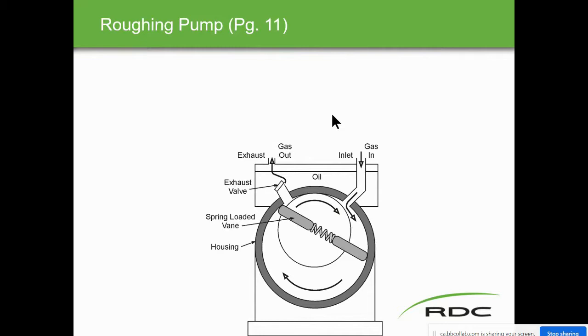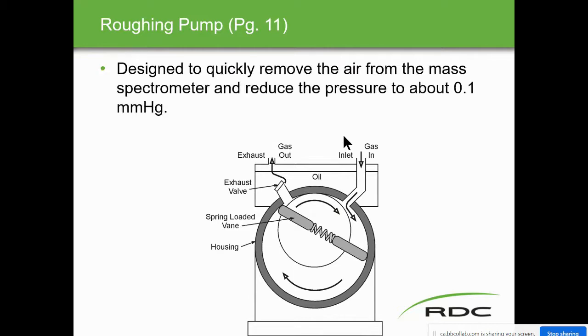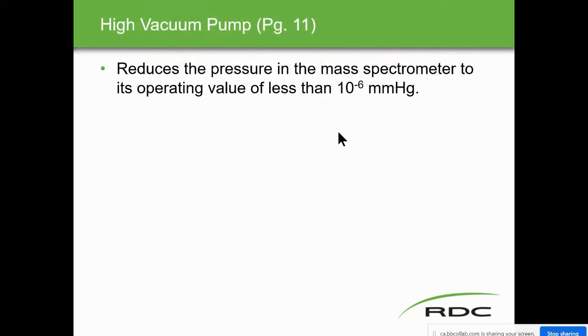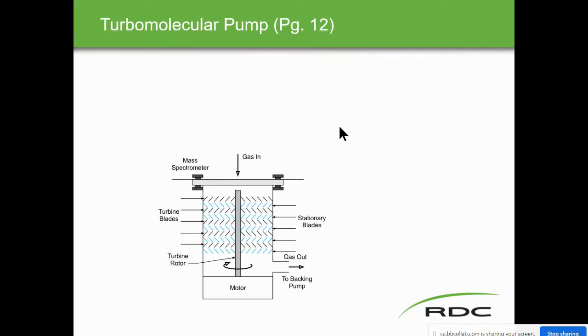On page ten, the high vacuum systems: the roughing pump starts first and takes pressure down to 0.1 millimeters of mercury. Because of the magnetic field and time-of-flight analyzers, we don't want any air in there — we don't want molecules bouncing off air. The high vacuum pump then removes the remaining traces of gas. These pumps maintain pressure less than 10⁻⁶ millimeters of mercury in the analyzer and detector, preventing contamination of air molecules mixing with the sample molecules.